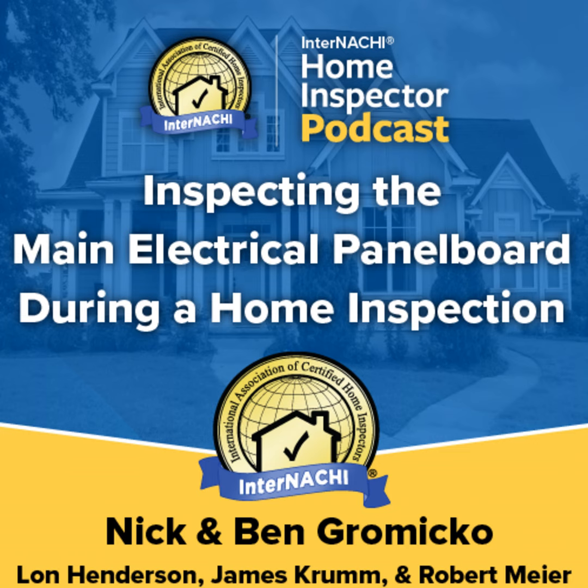Panel board size. Panel boards, or breaker panels, are measured by their maximum current carrying capacity given in amps and by the number of circuit breakers they can hold. Code requires services to be at least 100 amperes for homes. Generally, for most homes smaller than 3,500 square feet that are not heated electrically, a 200 amp panel with 40 breaker spaces provides enough power with some room for expansion.